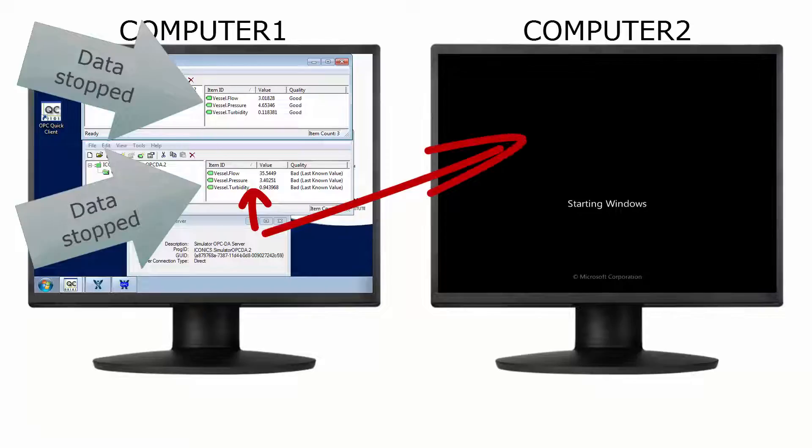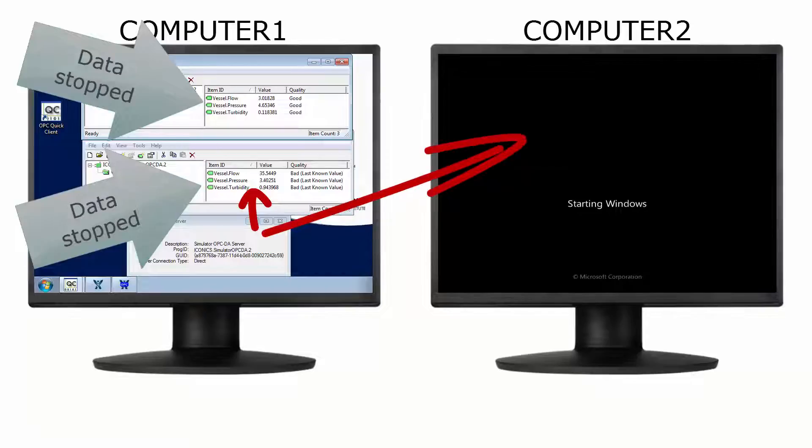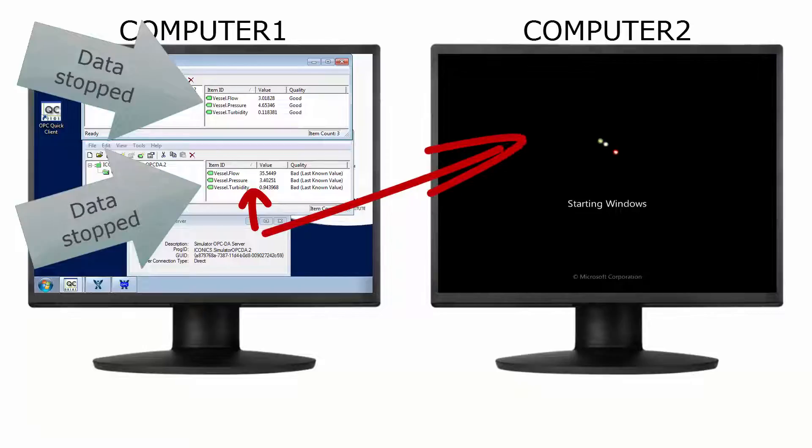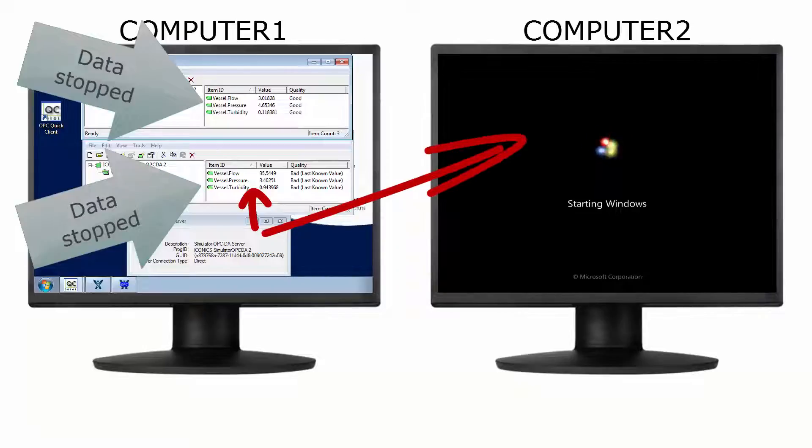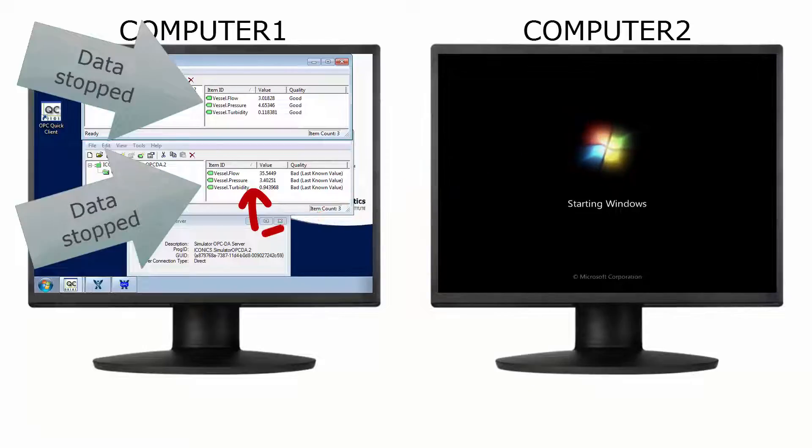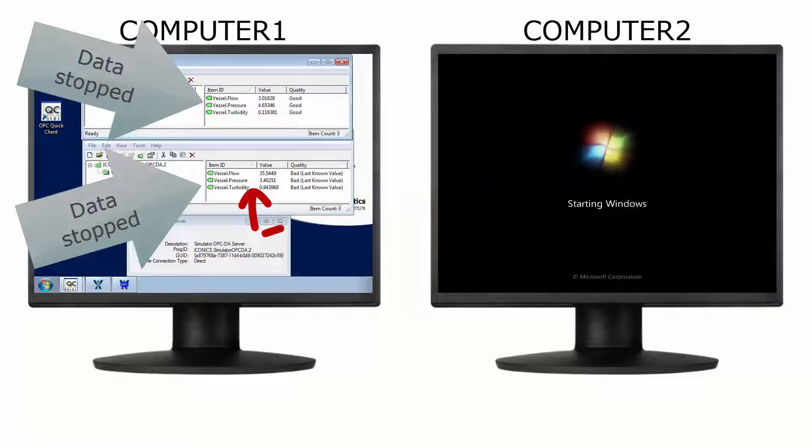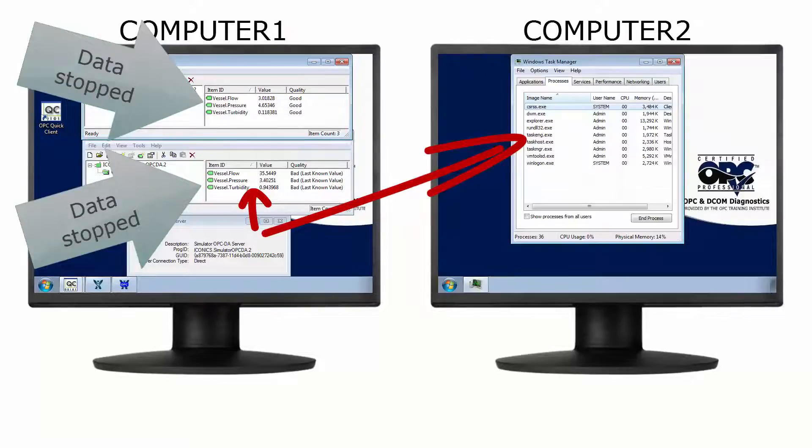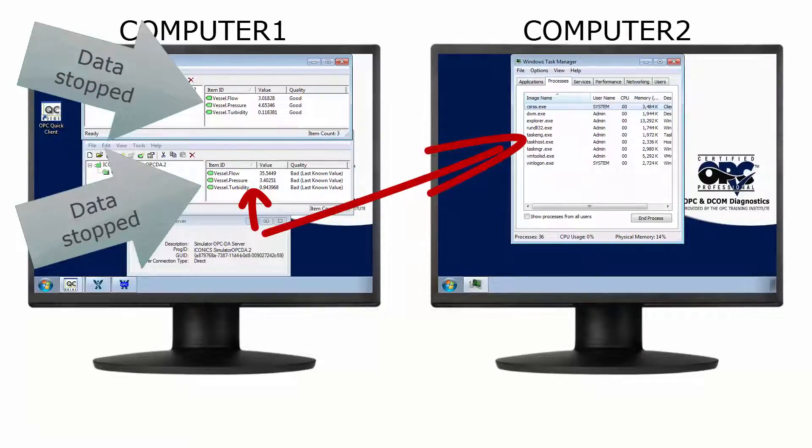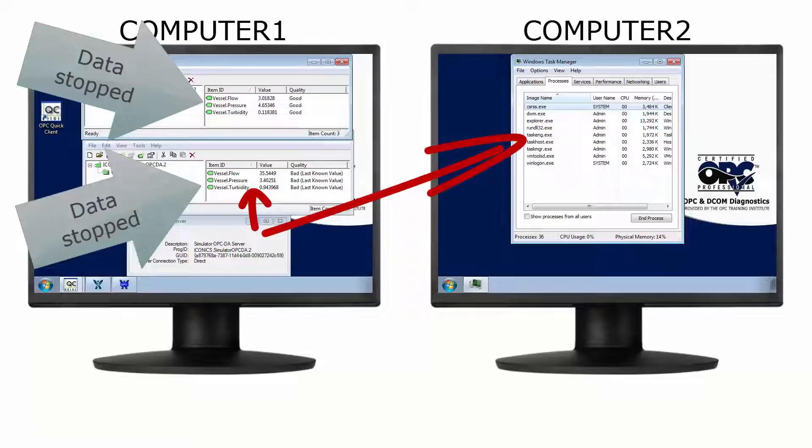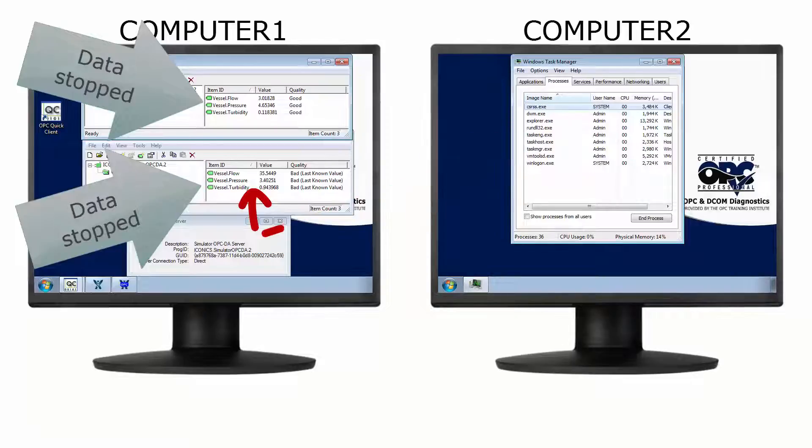Once again, OPC Expert recognizes the connection died. It immediately tells the OPC client there is a problem and sets the data quality to bad. OPC Expert keeps retrying again and again until it is finally successful.